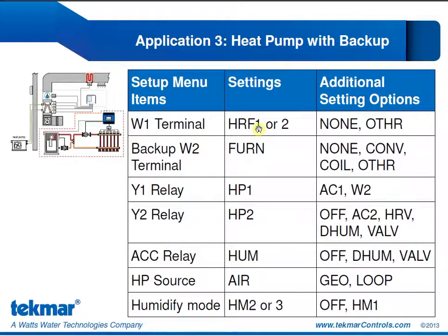These are the essential settings of this application. Again, if we are configuring it for a radiant system, the W1 terminal will be set for HRF 1 or 2 depending on the mass of the radiant floor. Our backup W2 terminal will be set to furnace, and this is because we need the fan operation for that electric strip backup. Y1 and Y2 relays are set for the heat pump stages 1 and 2. Our accessory relay is again set for the humidifier.